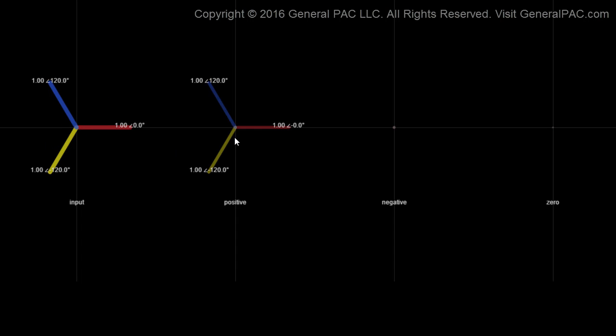We have an ABC phase sequence and a balanced system. When we have a balanced system, our positive sequence component is going to be identical to our system phasors. But our negative sequence component and our zero sequence components are both going to be zero. So for a balanced system, we should only have our positive sequence component and it should look exactly like our system phasors.